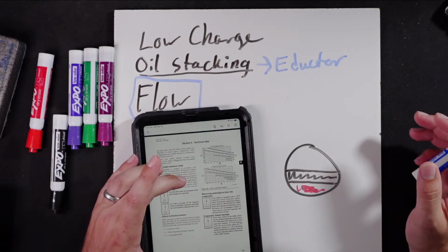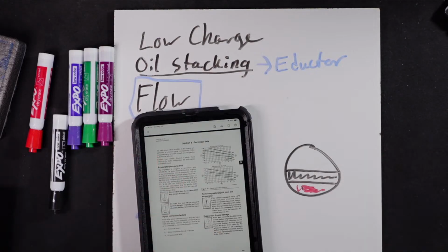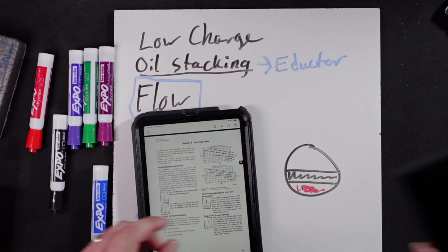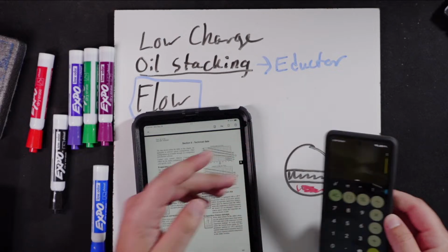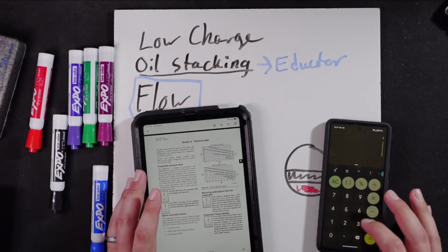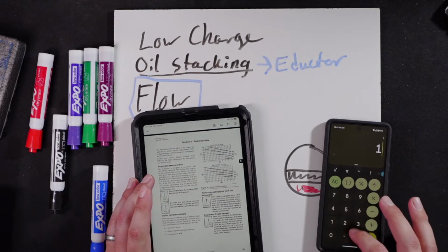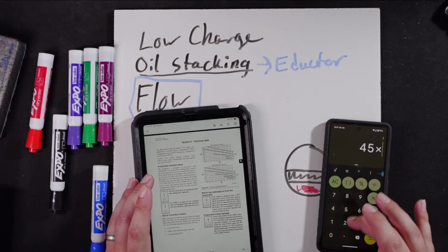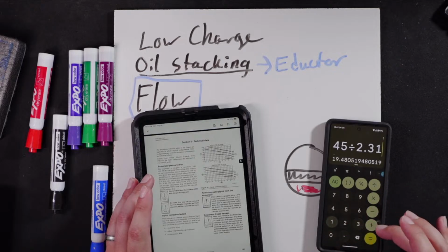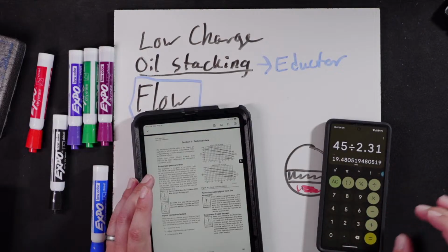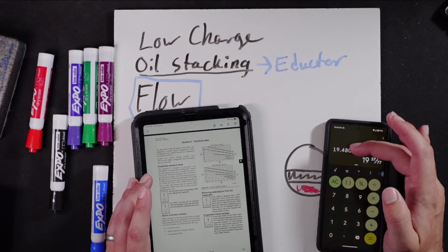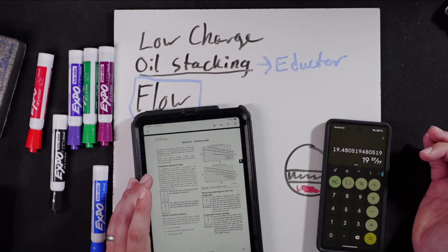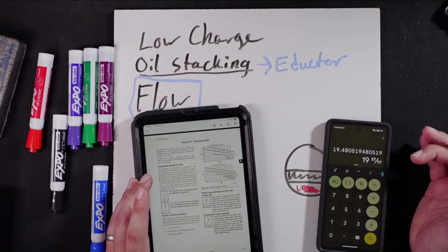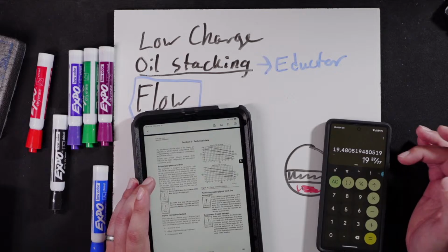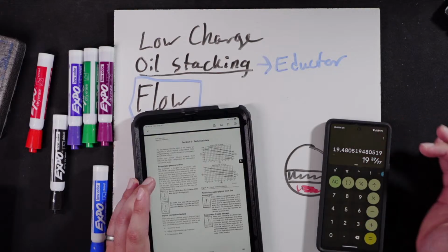We're going to divide 45 by 2.31. Get a calculator going. I never even considered pulling my tablet into this. This just kind of popped in my head as I got it going here. So we're gonna work through this live, okay? We're just having fun today. I'm experimenting. So we got 45 divided by 2.31. You could also use 0.433, which is another conversion. So that would be 19.4 PSID. 2 pass are limited to a maximum of 19.4. So basically 19.5 rounding up.